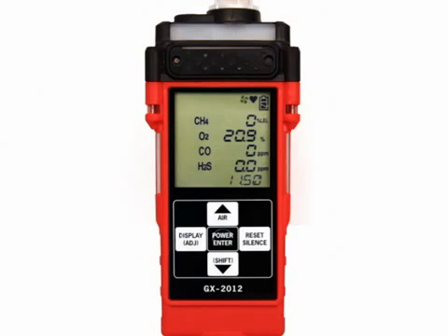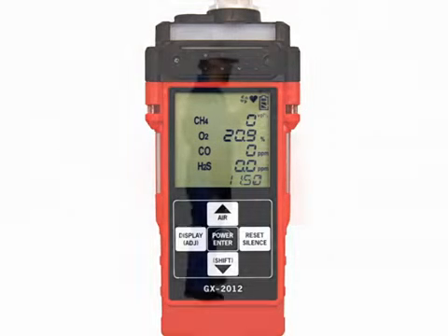In this case, the combustible gas channel will display the combustible gas concentration in % LEL up to 100% LEL. If the combustible gas concentration rises above 100% LEL, then the unit automatically begins displaying the concentration in % volume. If the combustible channel is set for % volume only, then there are no gas alarms for any detection channel.